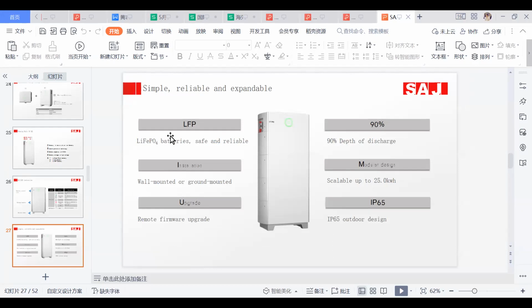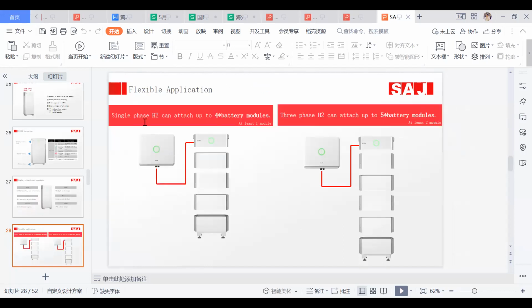And our batteries use lithium, and the maximal depth of discharge is 90%. For H2 inverters, it can scale up to 5 batteries, that is 25 kilowatt hour. Single phase H2 can be connected with 1 to 4 batteries. For 3-phase H2, it can be connected to 2 to 5 batteries. That means for 3-phase H2 inverters, you need at least 2 batteries to start the inverter.